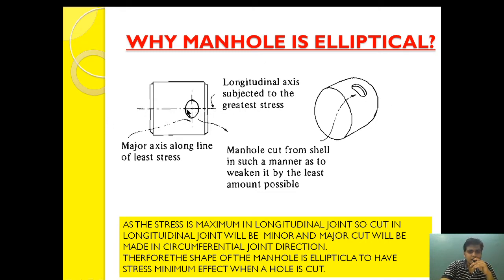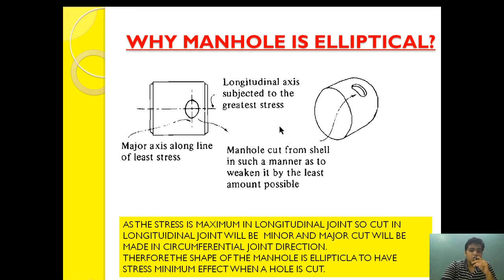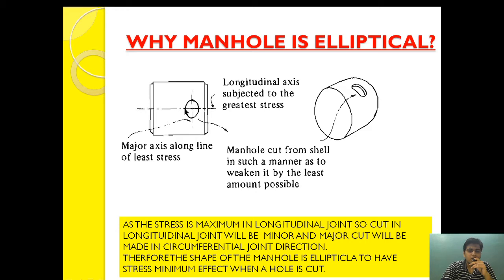Why is the manhole door elliptical? As you can see, this is the longitudinal joint and this is the circumferential joint. The manhole door is cut elliptical because, as I told you in my earlier video, the longitudinal stress is twice as compared to the circumferential stress. If the stress acting on the circumferential joint is 4 Newtons, it will be 8 Newtons in the longitudinal joint.